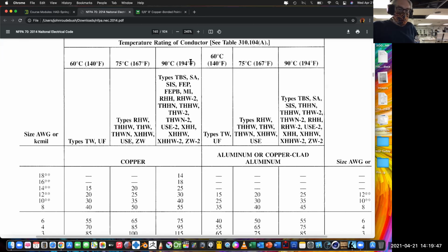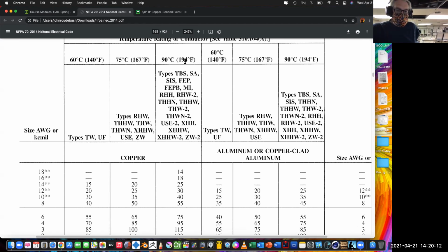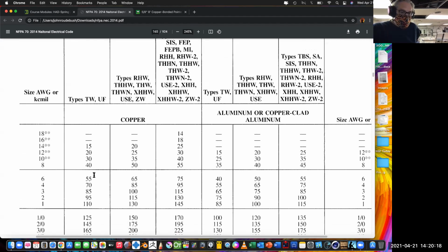We know that's bad. That's not something you want to stand out in the sun, right? So that's hot. If we felt that wire, it would burn our fingers, even though the insulation was there. But we're trying to use THWN-2 wire because it's versatile, right? It's a high temperature rated wire. And what does that mean? If we use number 6 THWN-2 wire, that means it can handle 75 amps until we derate it, of course.